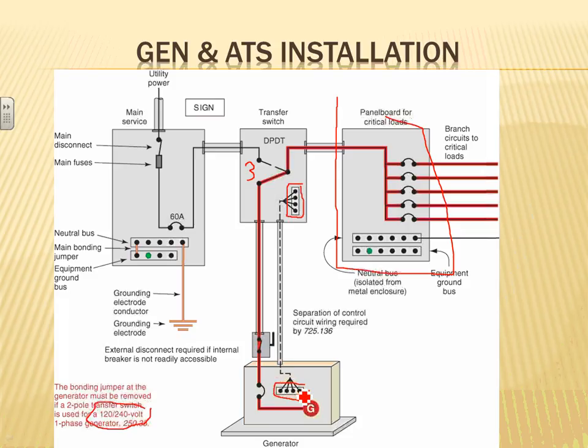I got a question. Yeah. Normally, when there are transfer switches, we have a make before break system. That's closed transition. Yeah, make before break. Or break before make. Ah, that's open transition. That's normally how we do it. If you have closed transition, then the utilities force you to have relaying because of feedback and so forth. There's a lot of requirements, it becomes more expensive. You basically have to meet all the requirements in parallel. Yes. And remember, 99% of the generators that we specify are for emergency power for buildings, and they don't switch it.